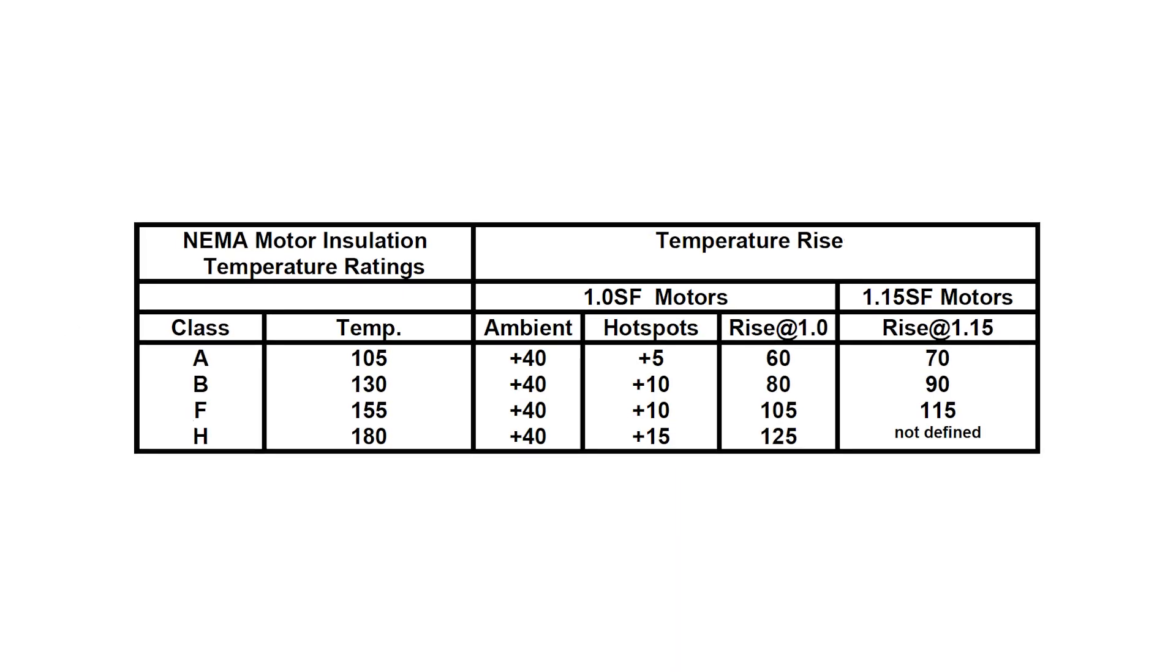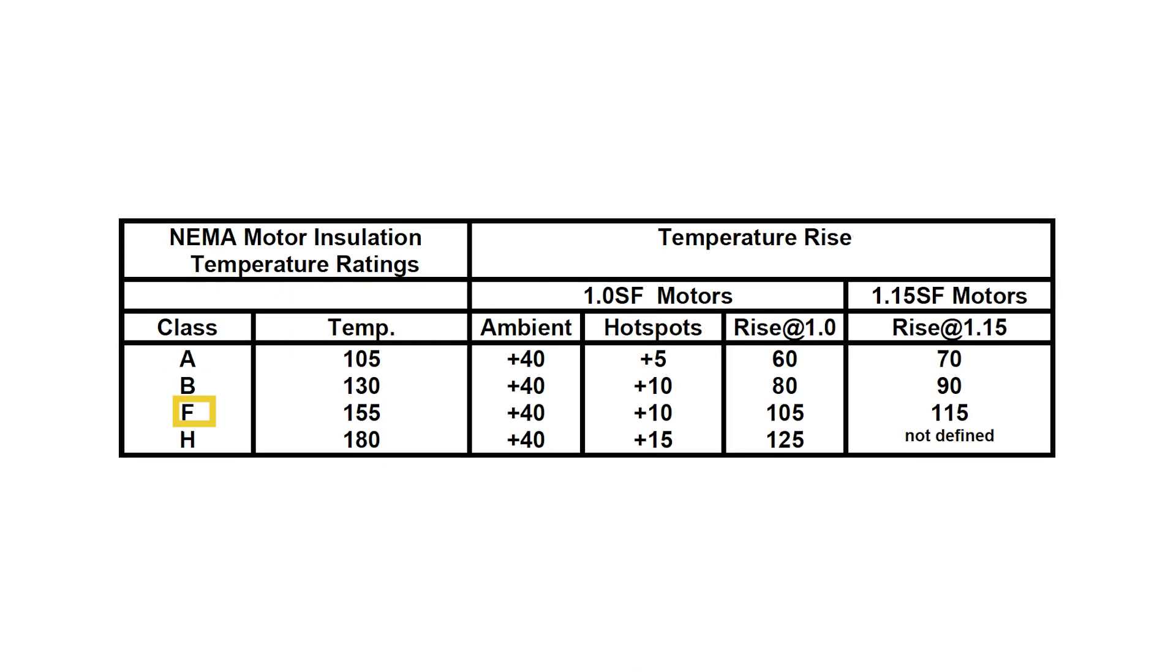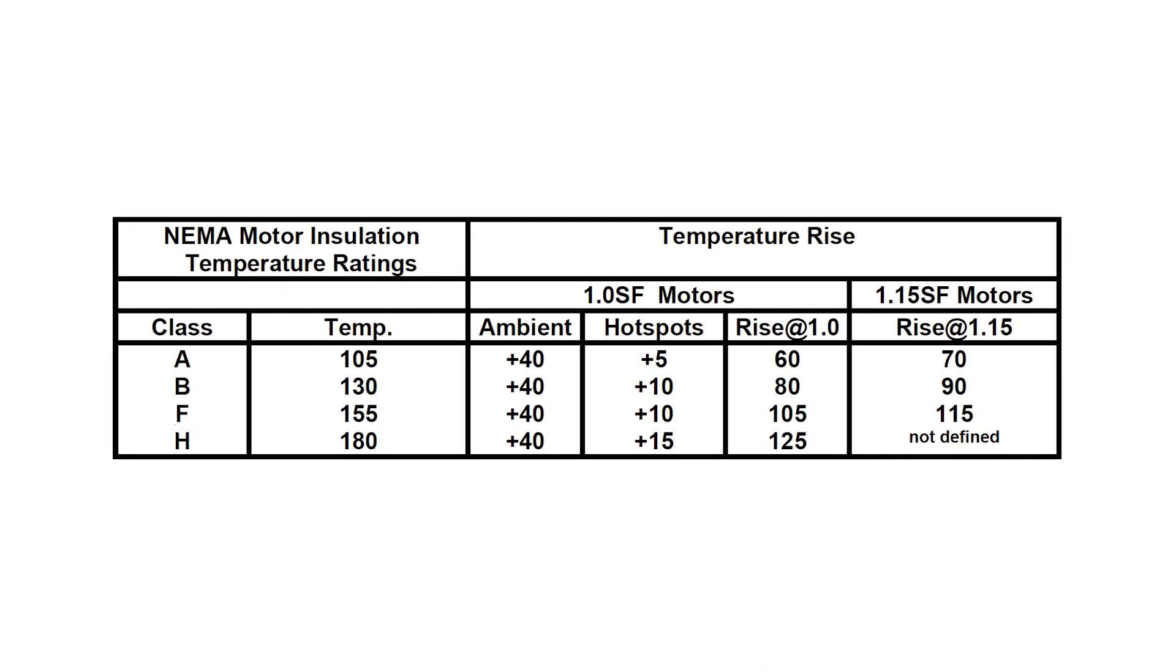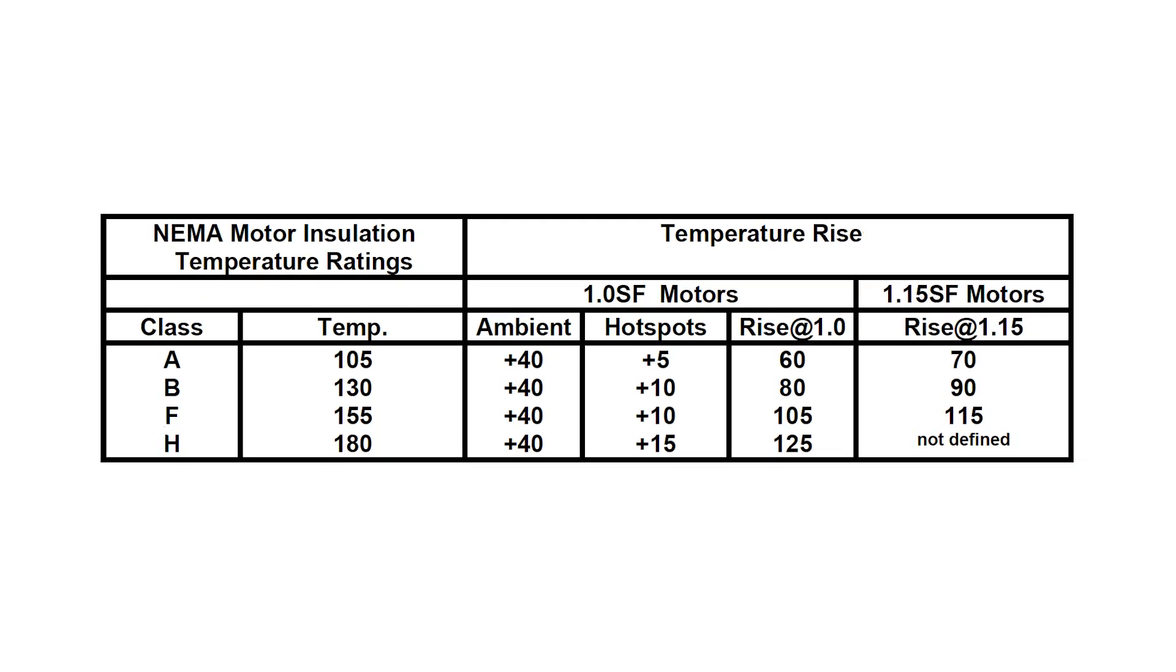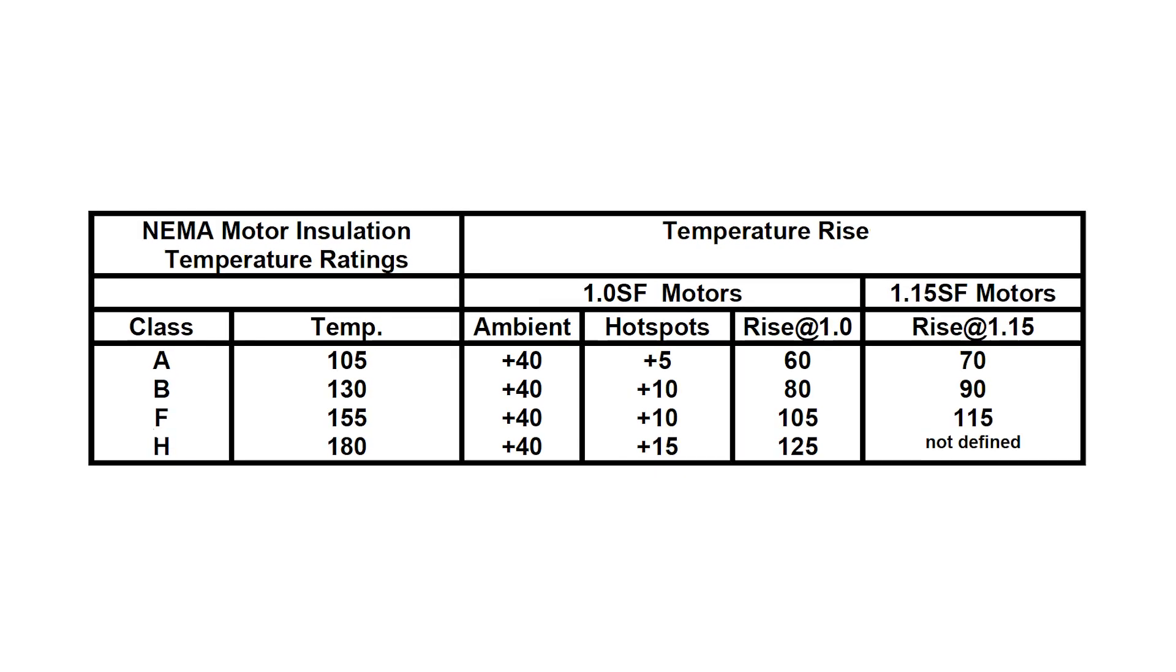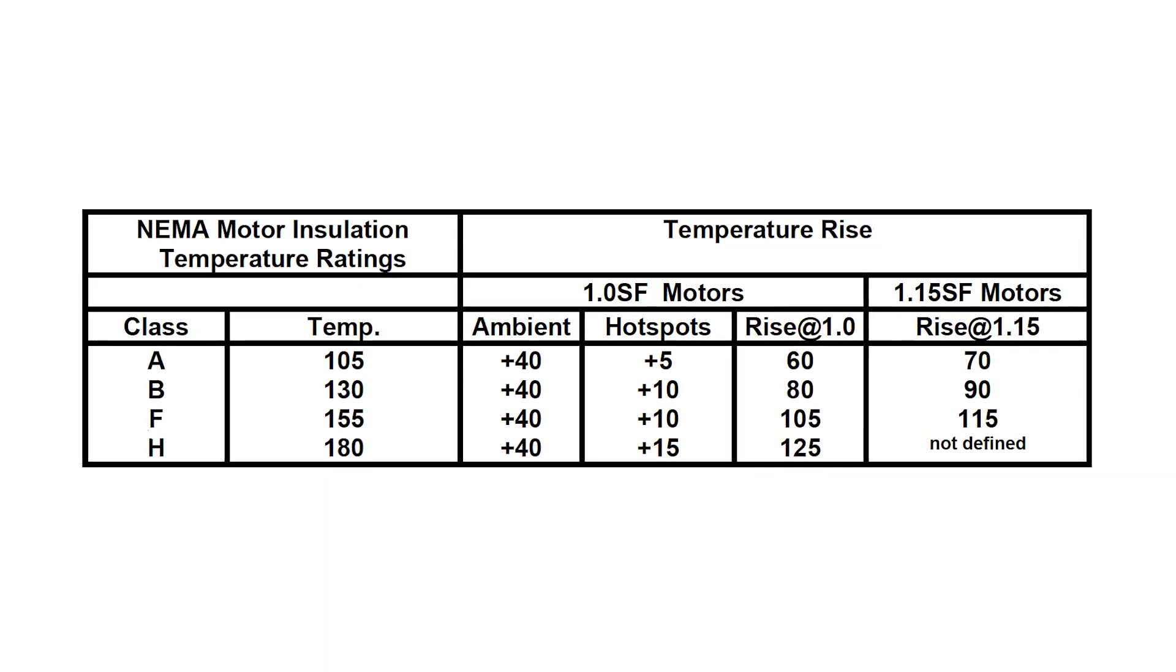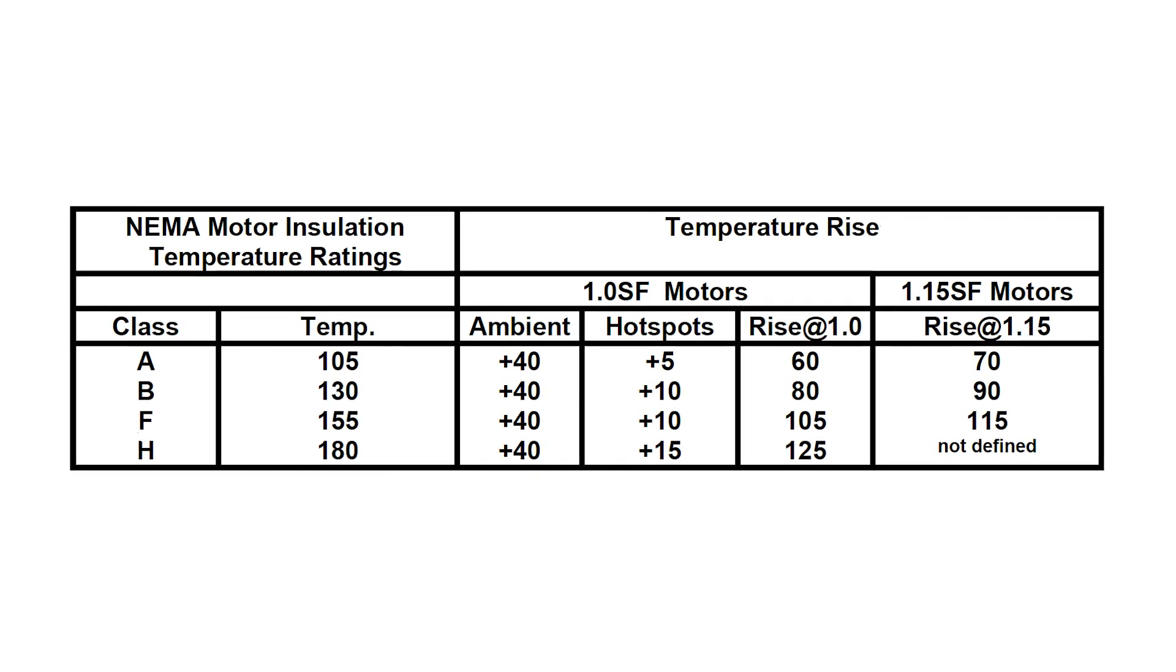The NEMA insulation classes currently in use are A, B, F, and H, although newer motors are rarely built with Class A insulation, which has a maximum winding temperature of 105 degrees C. The maximum winding temperature increases by 25 degrees C with each step up in insulation class.